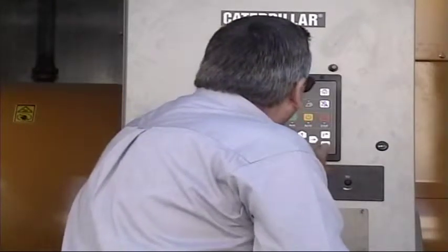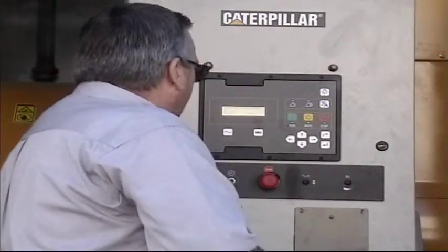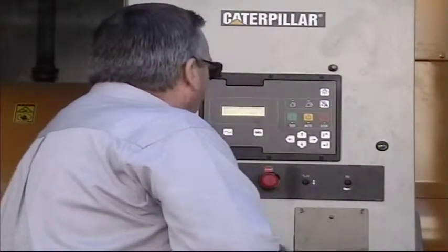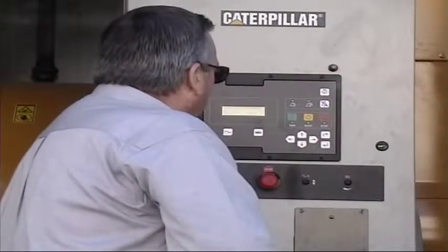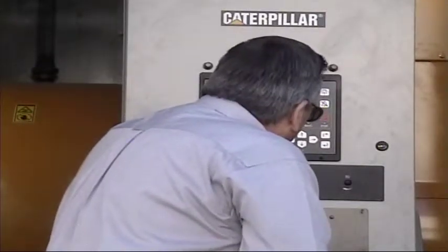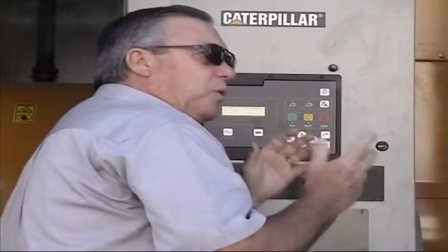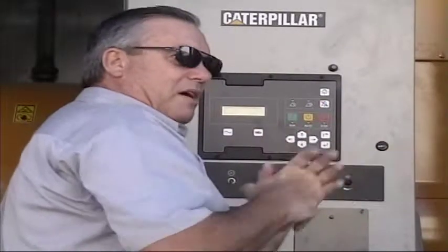And it says I got a genset control, 4 actives. Okay, it says emergency stop switch activated. So what do I do to get rid of the emergency stop? Well, what I've got to do is get this. The first thing I would do is put it in stop, because that's the only way I'm going to be able to clear anything. So I put it in stop.